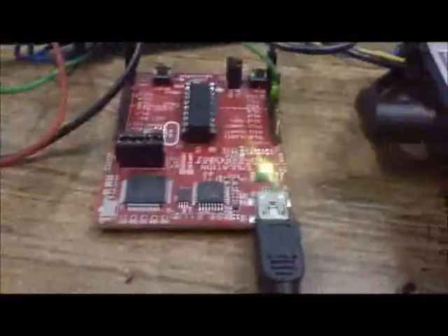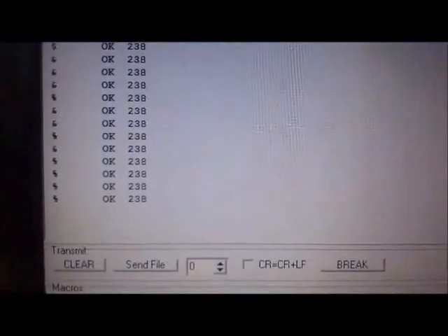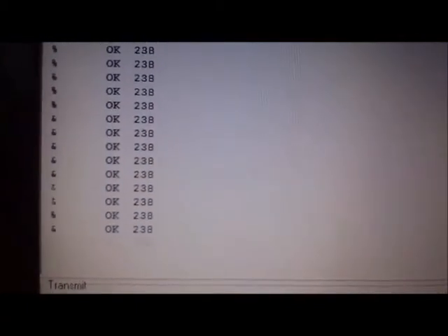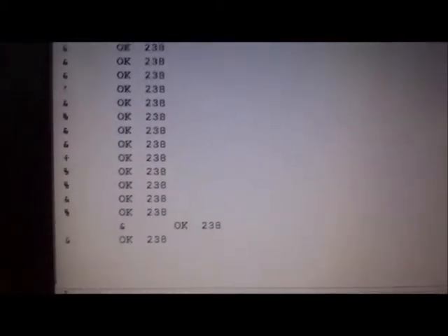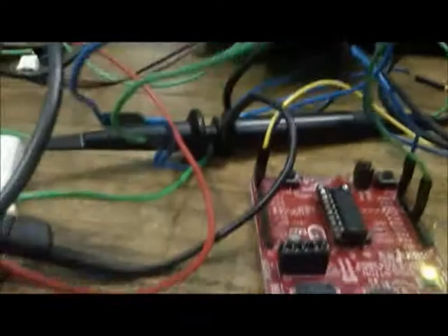These values are compared with the normal voltage taken as a voltage threshold, and the classification of the signal is made accordingly. Anything more than the threshold is considered as swell and less than is considered as sag. When a voltage fluctuation occurs for a very small number of cycles, it is considered as a transient.